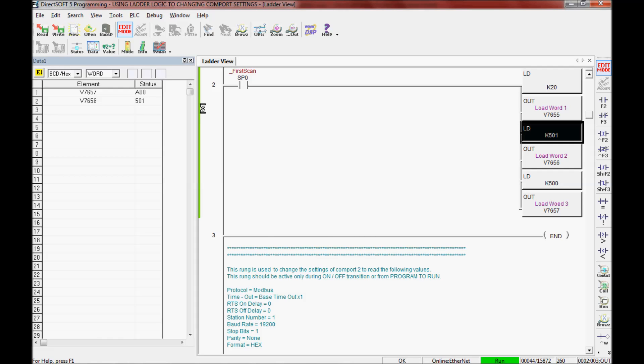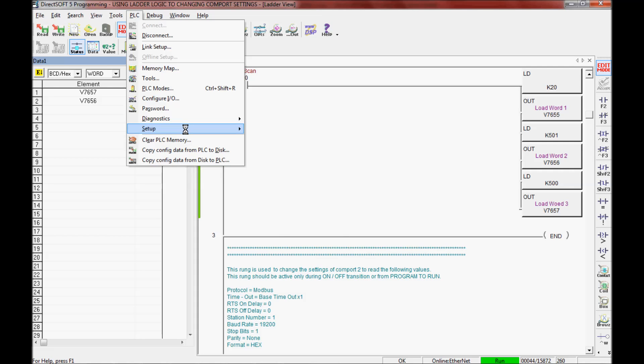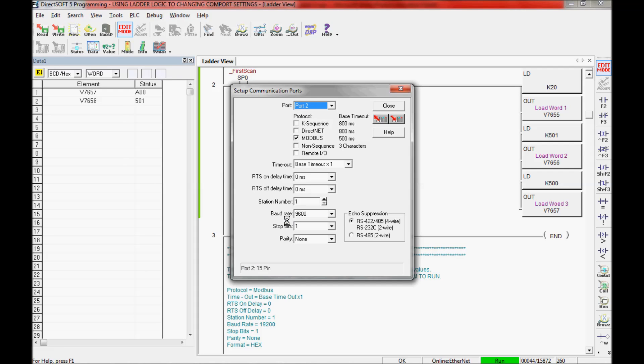I'm going to go to program mode, then come back to run mode. You can see my value hasn't changed yet — I'll click OK. And now you can see my value has changed. That A up here in word number 3 changed briefly to a 5 — I'll go over that in a few minutes. Coming back down to the second COM port: K-sequence and DirectNET have been unchecked, I'm at a baud rate of 9600, and my parity is none. I'll close this out.